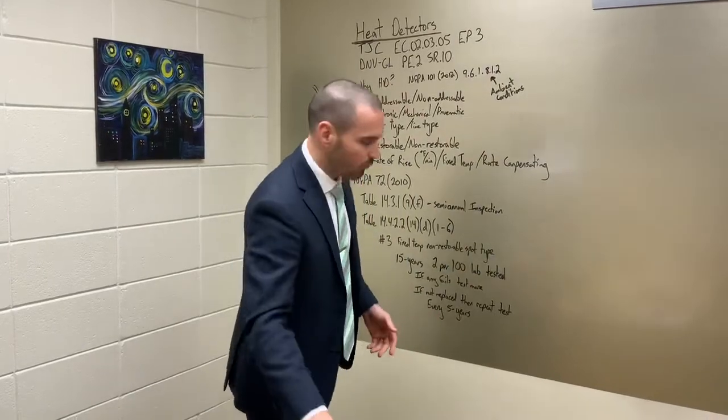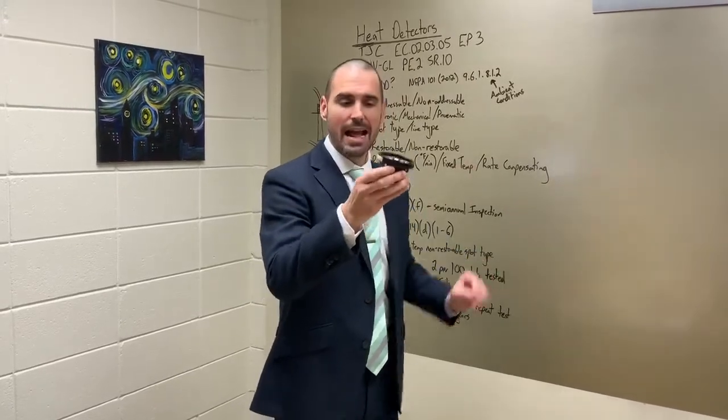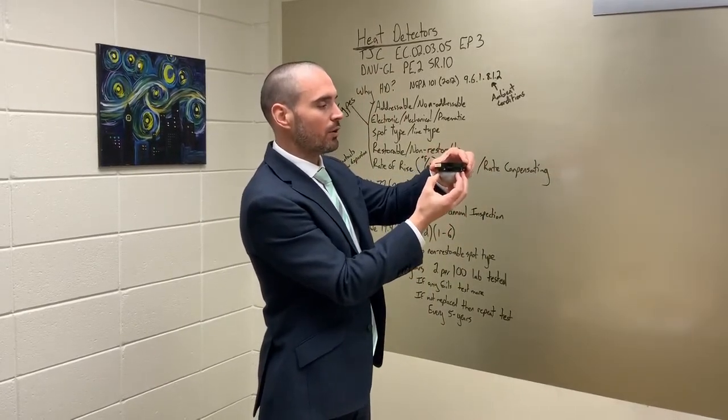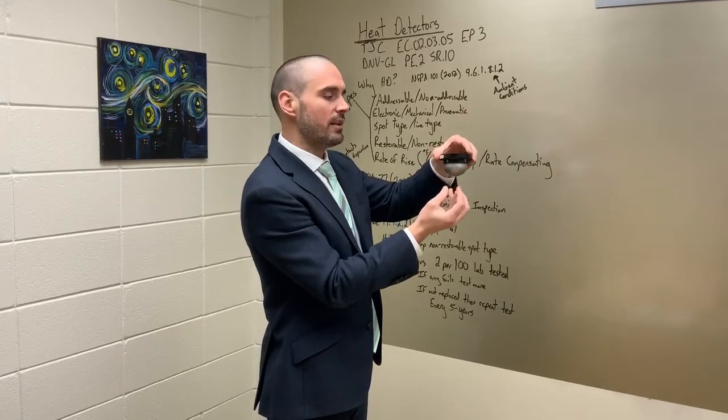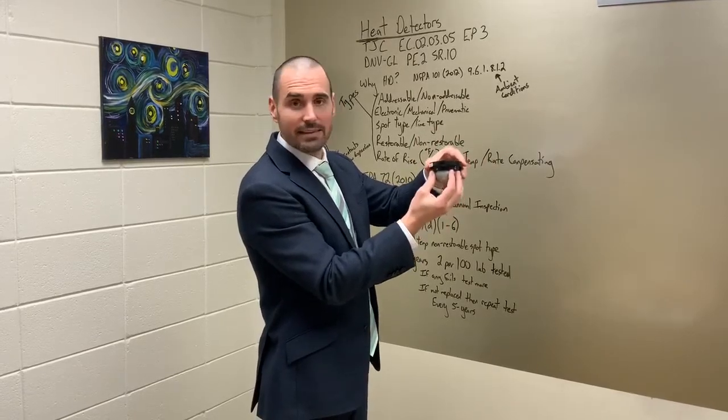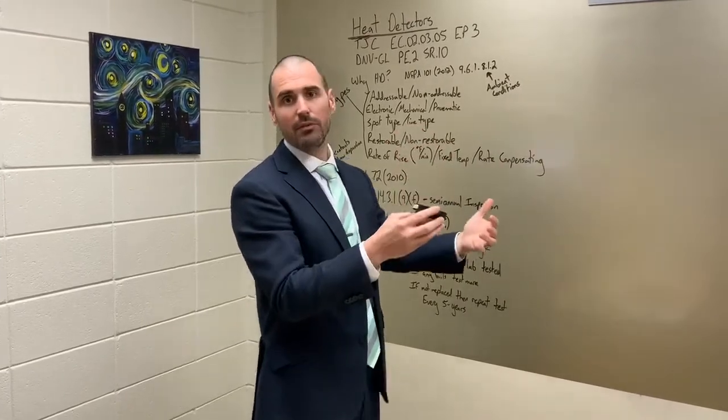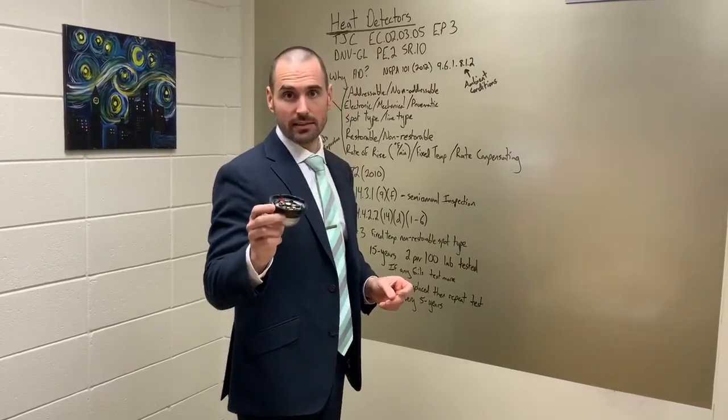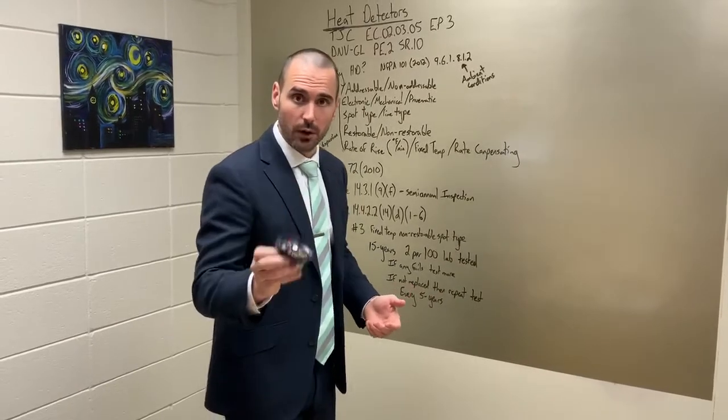Where we see problems are with our non-restorable spot type detectors. This is actually both. This is a rate of rise restorable and a fixed temp non-restorable. So the rate of rise in this is pressure builds up inside of this air chamber and it vents out of the top. When pressure builds up faster than it can vent out, it triggers an alarm. It also has a fixed temperature. When it hits a certain temperature, then it triggers the alarm as well. But that is a thermal link. There's a spring inside of here, it melts it and that spring releases and activates. So that one can't be replaced. You gotta throw it away. What's most common is that these aren't tested. If you check your reports and you have these, a lot of times it will say unable to test non-restorable device. That is false. It's absolutely false.